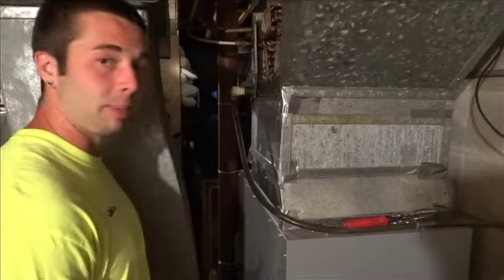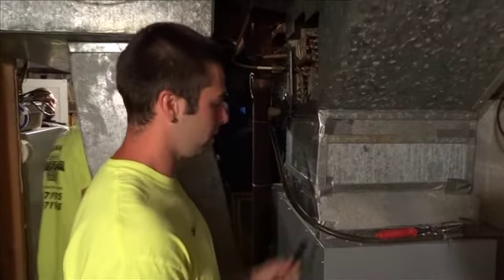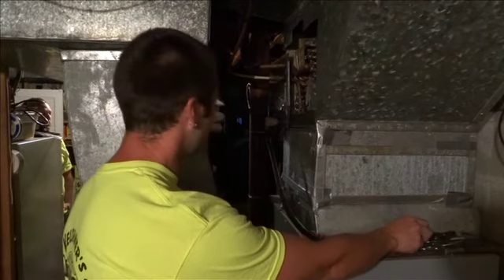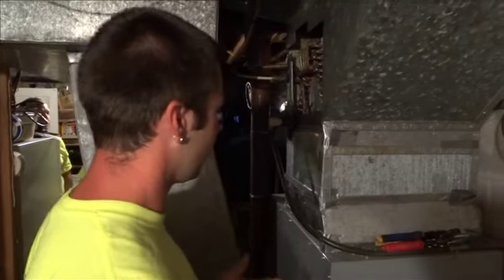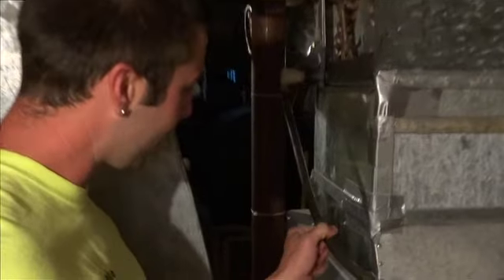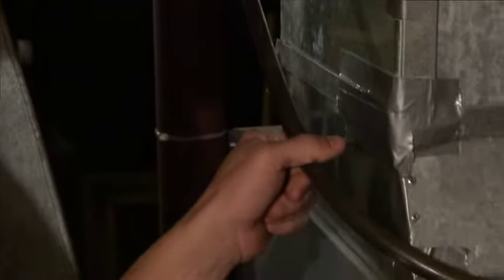All right, next we're going to take apart the drain line here. Take the drain fitting off of the A coil. Make sure that's all clean. The drain line we got here is pretty old and looks like there's a lot of mildew and mold built up in it, so we're going to replace that.